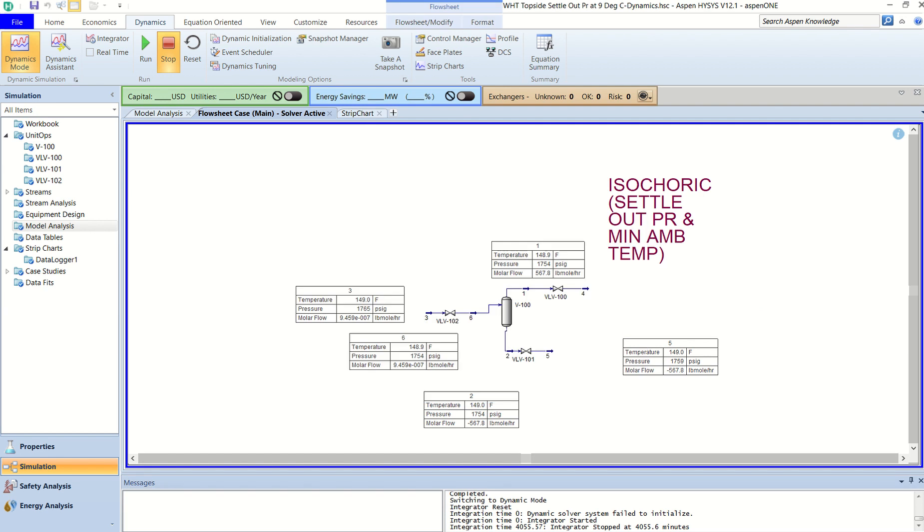So what is isochoric blowdown all about? When we do blowdown, there is one fire case, there is adiabatic depressurization, and there is isochoric depressurization. Isochoric depressurization basically determines the MDMT of the pipe and of the blowdown valve.